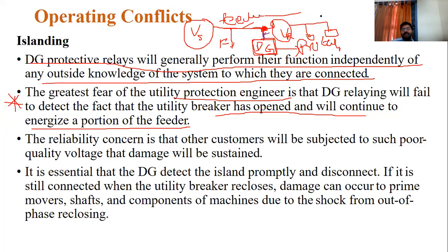That may lead to the entire load voltage and load being driven by this DG. But actually speaking, this DG's capacity is not enough to drive this load. This is the islanding. That may lead to sudden changes in the voltage to this load, a very low voltage to this load, that leads to a voltage sag and may damage the system. At the same time, this DG is also damaged. You understand? So this feeder is open when the fault occurs in the feeder, but DG relaying failed to operate. That means the DG still continues to drive these loads, but the DG capacity does not match these loads.